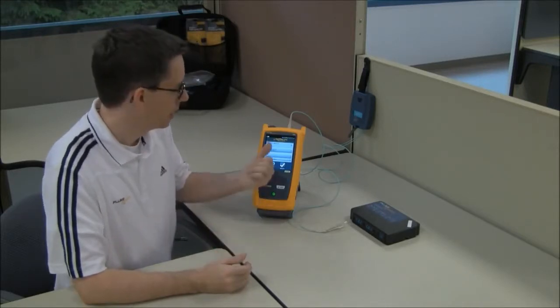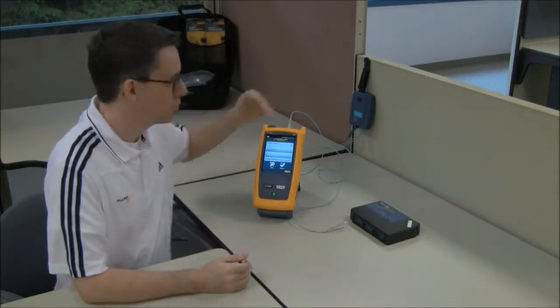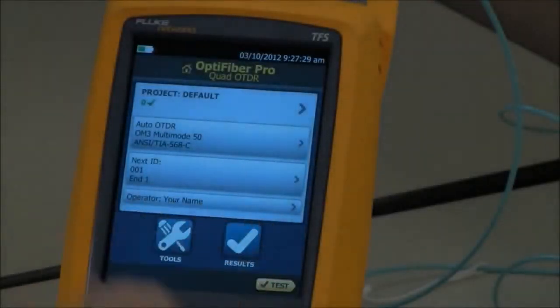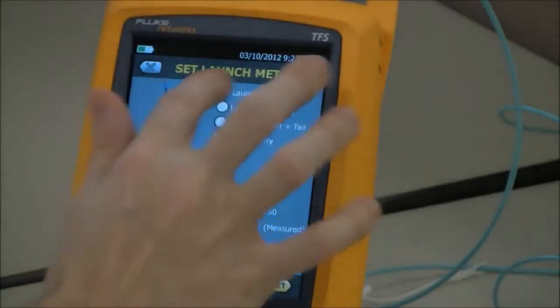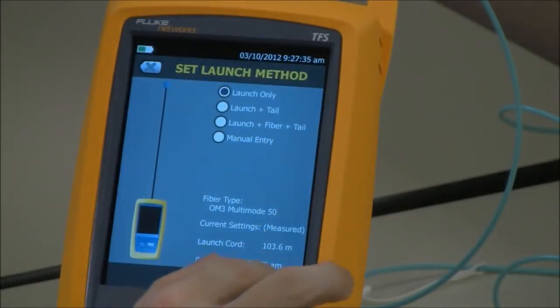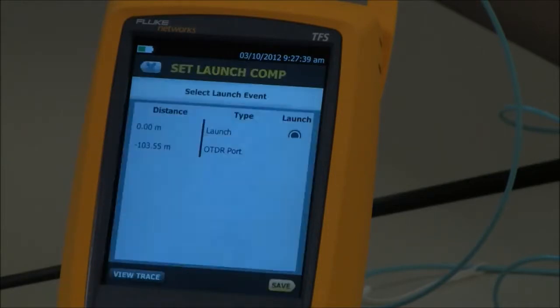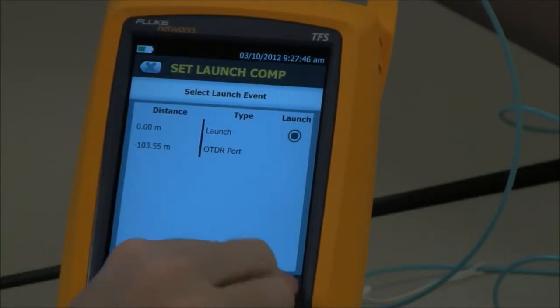First, let's set the launch compensation so the length of our launch fiber is not included in our measurement. Tools > Set launch compensation > Launch only > Set. OTDR port is good. We see that my launch fiber is 103.55 meters, so I'm going to store that.